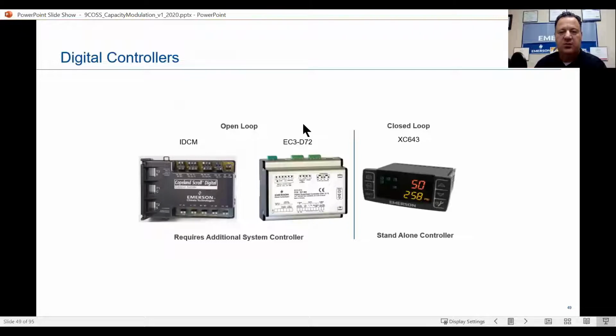Controllers. On the left-hand side, we have 2 of them, and I'll show you what that looks like. Open loop means that there's some type of third-party controller of some sort out there, whether it be a thermostat or someone else's controller out there with a set point. This is the IDCM, and I'll talk about that a little bit more. This, again, requires an additional system controller, and then we have the EC3, DC72 or D72, and I'll talk a little bit more about that.